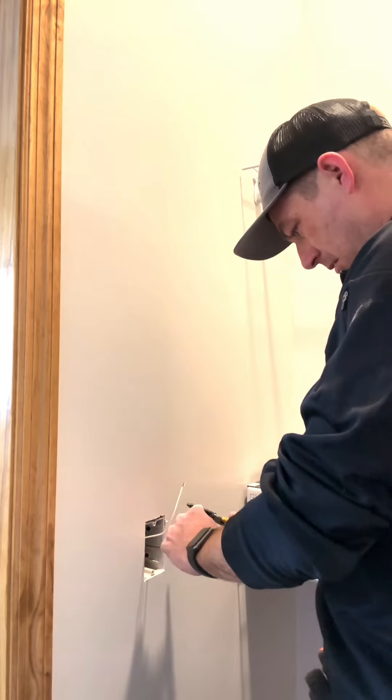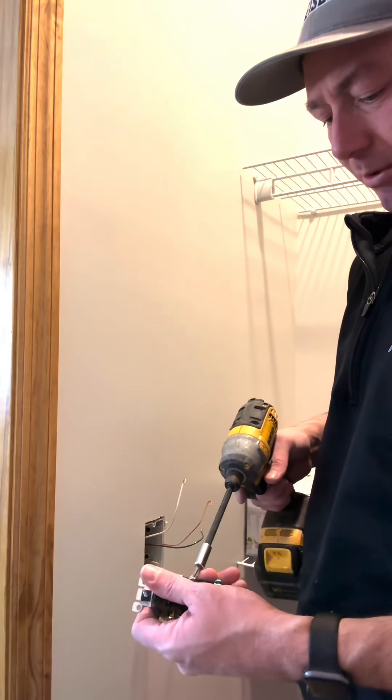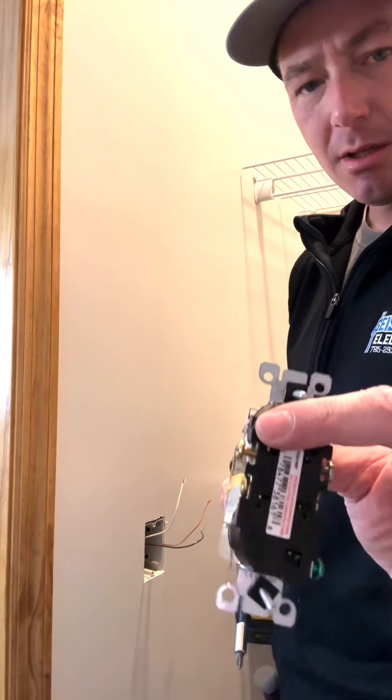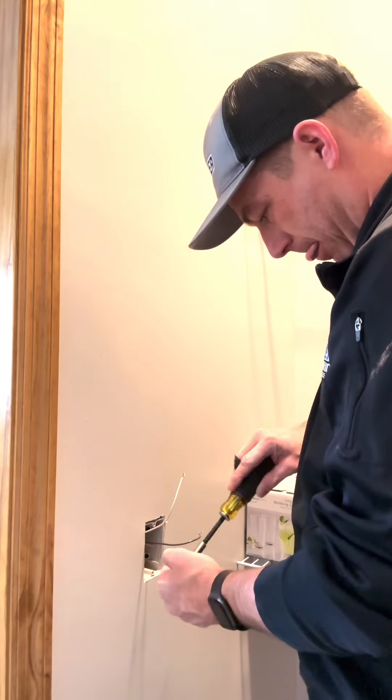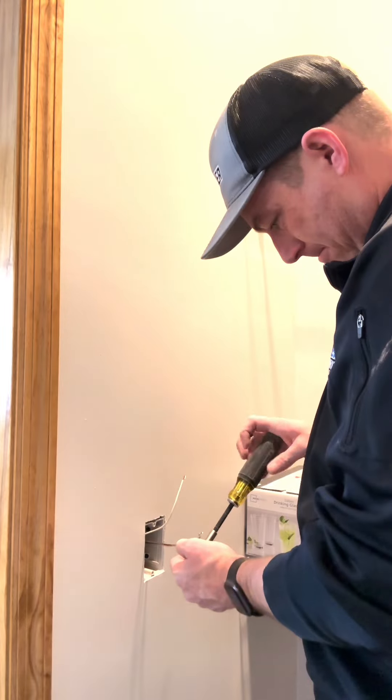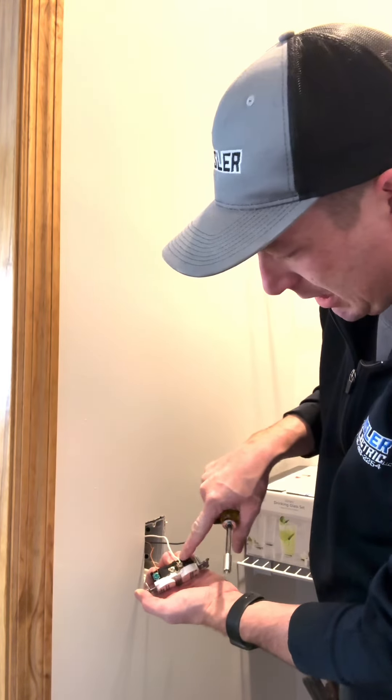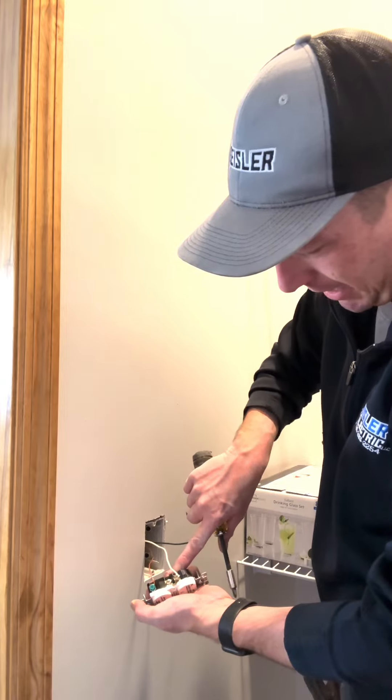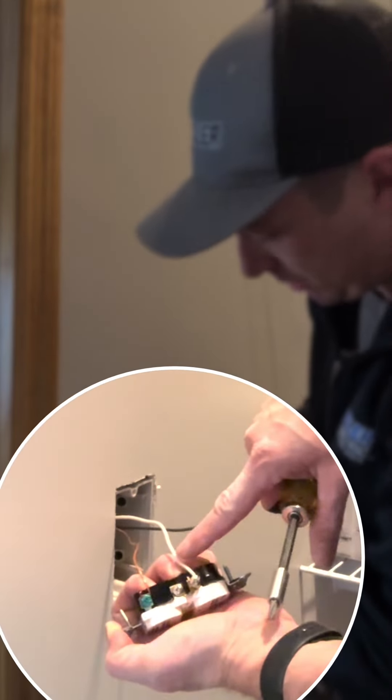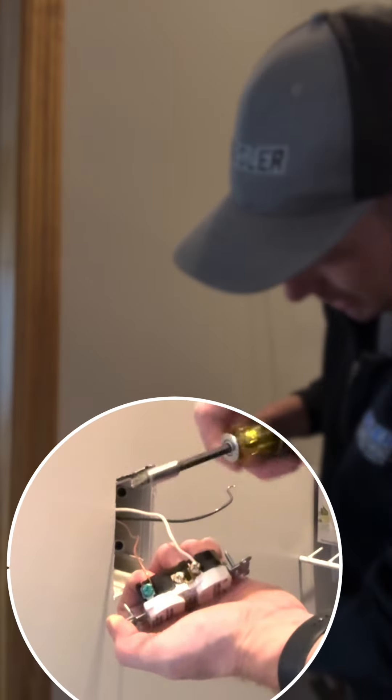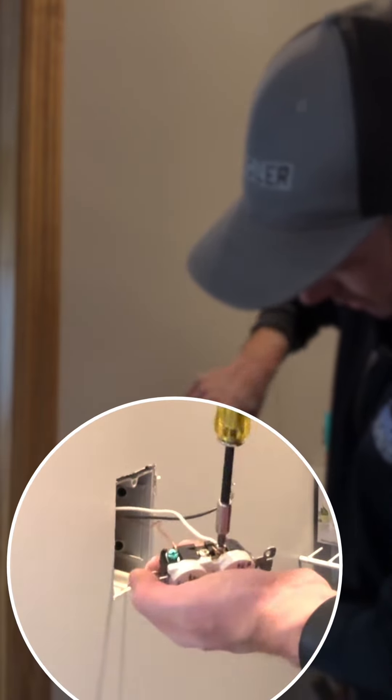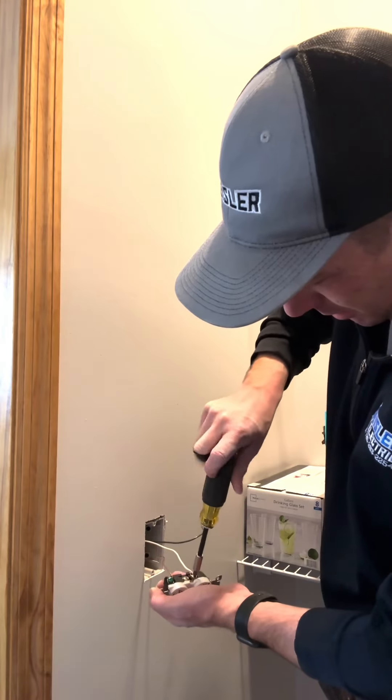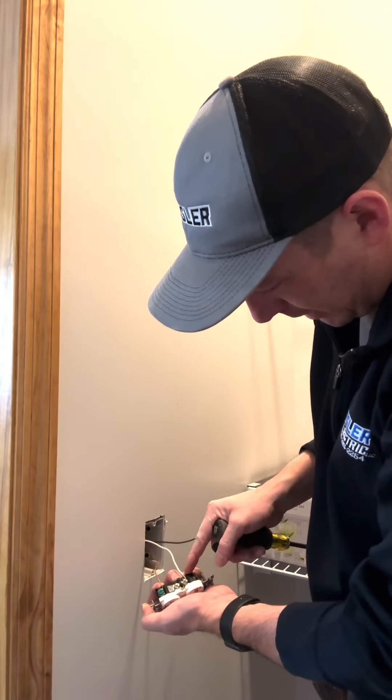Anytime you're doing receptacles where there's only one wire, always get rid of that unused screw. Another thing to watch out for on these receptacles: if you ever have copper sticking out past this plastic part, you need to redo it. You never want copper showing. In addition to that, you never want to have this insulation underneath that screw. So it needs to be all copper under the screw and then no copper past this plastic part, about an eighth of an inch there.